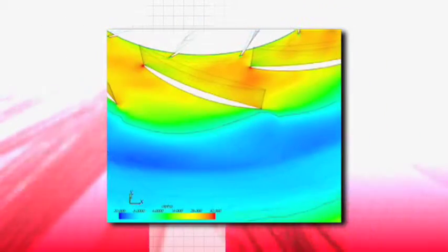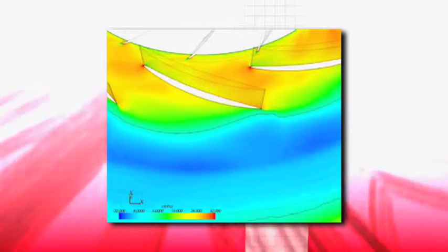The next fundamental component, the diffuser, serves a dual purpose. First, it converts the kinetic energy or velocity into potential energy or pressure. As the fluid particle proceeds through the diffuser, velocity decreases and static pressure increases. Again, the designer tries to accomplish this with minimal losses. The second objective of the diffuser is to act as a coupling device between the impeller and the scroll volute. Quite simply, the diffuser prepares the flow field coming off of the impeller for collection in the volute.